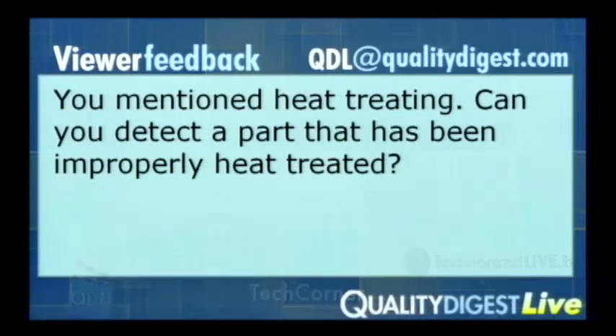A question came in: you mentioned heat treating — can you detect a part that has been improperly heat treated, not just untreated? Yes, we can find parts that have been improperly heat treated. We'd take several hundred of the proper value and look for deviations outside of that. Anything that affects the mass, stiffness, or damping affects the resonant peaks. For heat treating level, we can typically find values exceeding a Rockwell C scale of 5 — so if your range was 40 to 50, we can separate parts above 50 or below 40. The cost for this system is in the low 40s, and the fully automatic system is in the low 70s.